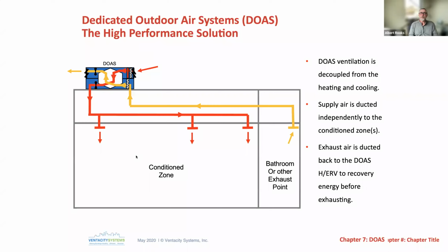And then they go inside the building and put in some mini splits in selected areas, or they do some VRF or something else kind of heat pump based, right? And essentially that combination has cut the building load in half by a literal 50%. And in those cases, they're adding cooling and they're increasing fresh air volume. And it's super simple. All they're doing is placing a unit on top, setting an airflow, not for conditioning airflow. Now this is ventilation airflow, so they need a fraction of the airflow. The energy penalty goes away because they're not picking up outdoor air and burning gas to lift that outdoor air and pushing it in the building and not recovering any energy after that transaction. Now they're recovering all that energy and redirecting it back in the building. Cutting the building load in half works really well. And then with half size load, they can easily pick up that load by mini splits or VRF.